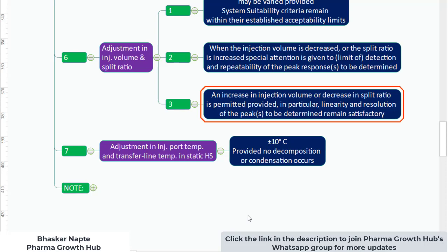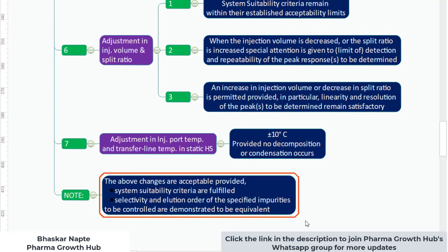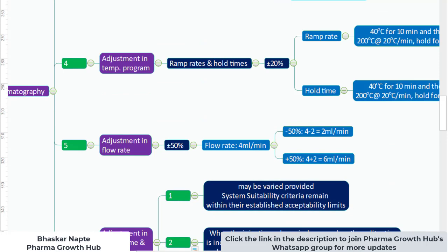An important note: whatever changes you want to propose, ensure that the above changes are acceptable only when system suitability criteria are fulfilled. Without meeting system suitability criteria, you cannot make any change. Additionally, the selectivity and elution order of specified impurities to be controlled must be demonstrated to be equivalent. If these conditions are met, you are free to make changes to gas chromatography parameters.